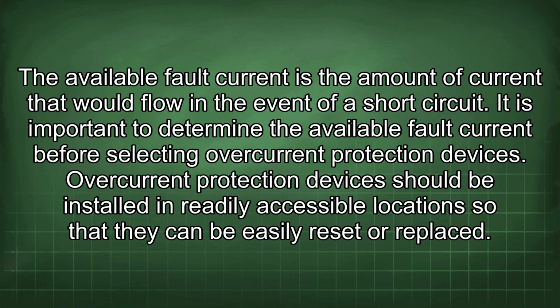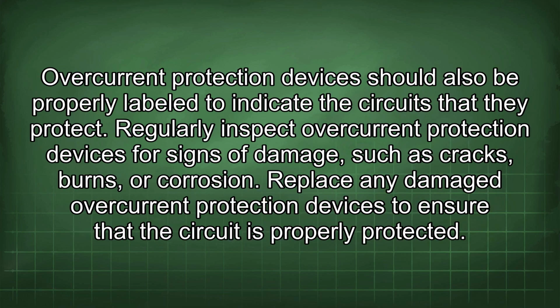Overcurrent protection devices should be installed in readily accessible locations so that they can be easily reset or replaced. They should also be properly labeled to indicate the circuits that they protect. Regularly inspect overcurrent protection devices for signs of damage such as cracks, burns, or corrosion. Replace any damaged overcurrent protection devices to ensure that the circuit is properly protected.